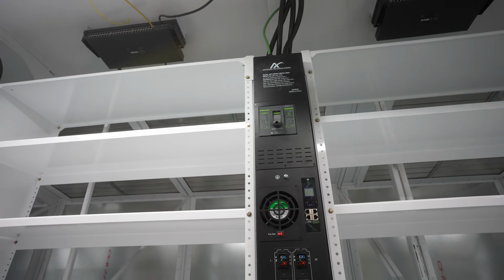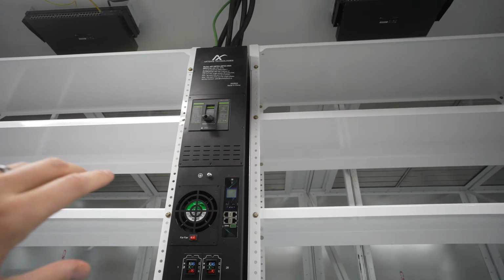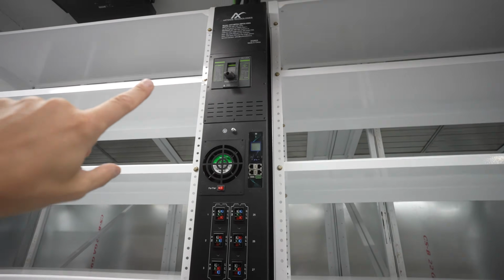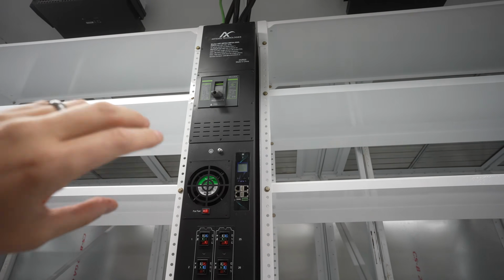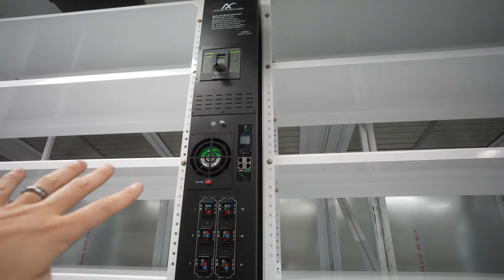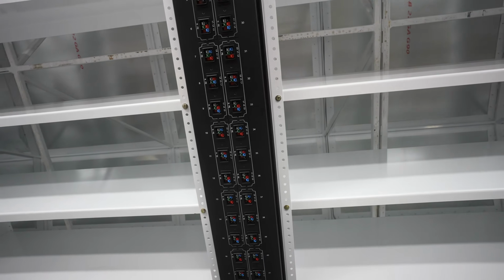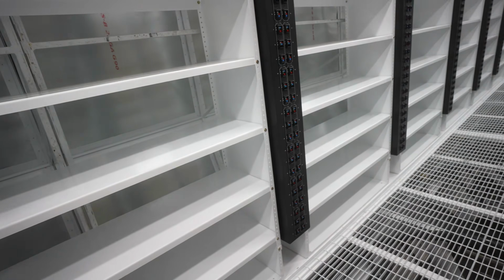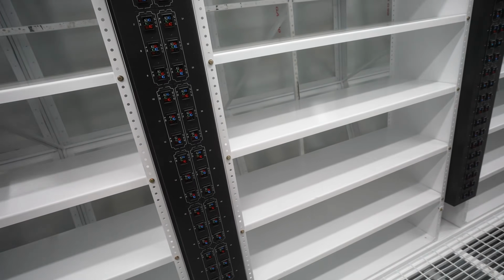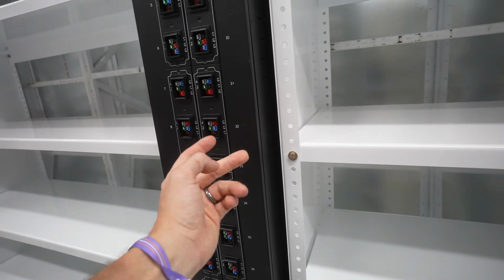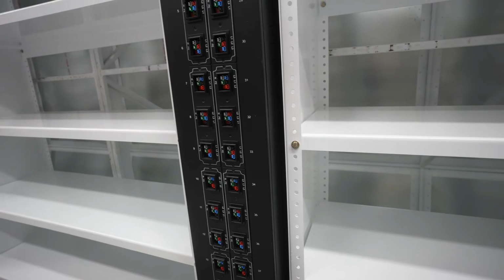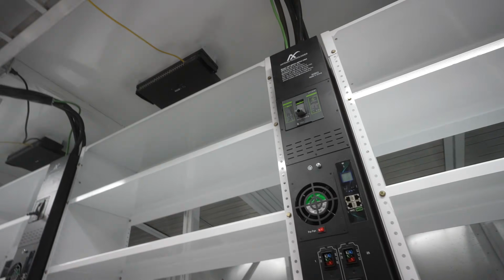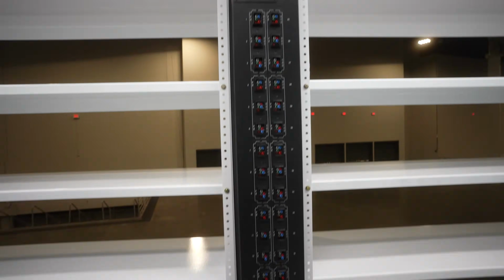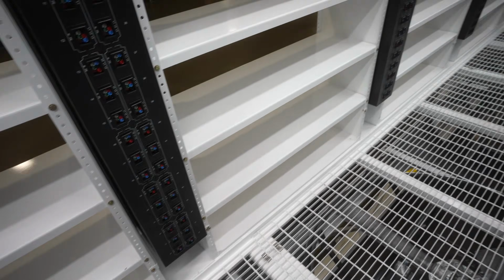That doesn't apply to a continuous use transformer, so you can just get one of those. Technically, this thing supports 4. Now these 350s already did the 80% rule, so you can do that at 4.5. So technically, I would say you can run this whole thing at 5 megawatts maximum. Then these guys are not going to be 80%, they'll probably be like 2, 3%, something like that. So this is basically a 5 megawatt container.